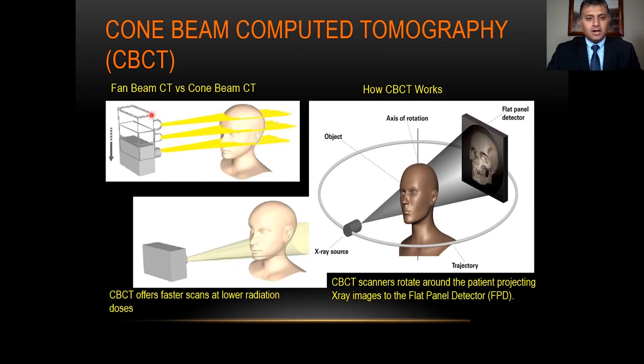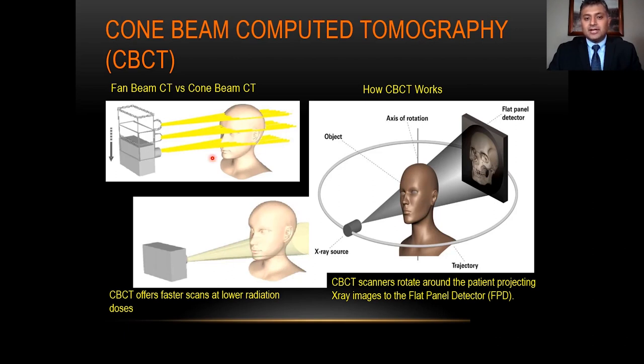Let's quickly review the difference between fan beam CT — the type used in hospital CT, medical CT, or multi-detector CT — where the beam shape is like a thin, flat fan that has to spiral around the patient's head multiple times to image the maxillofacial area. Cone beam CT, just like the name says, has an X-ray beam shaped like a cone. It can cover a much larger surface area, and one quick spin around the patient's head captures the maxillofacial and mandibular area. Advantages include quicker scanning at much lower radiation dose compared to hospital CT.